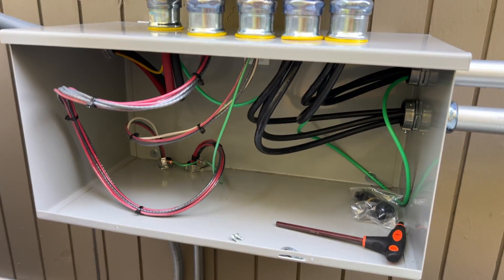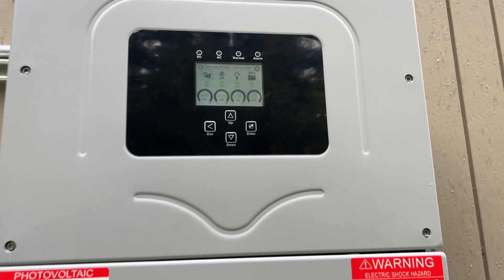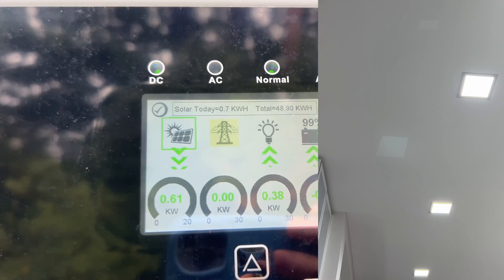The wiring of Sol-Ark is now finished and here is the final result with the protective cover. Now we can test the setup — I'm going to simulate a power outage by flipping the 100-amp breaker which is powering Sol-Ark, and it immediately switches to PV power and battery backup.